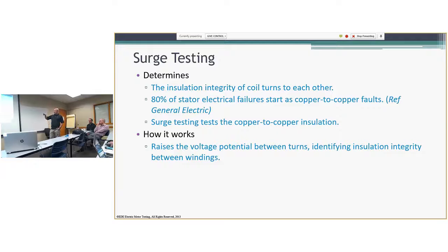So we raise the voltage potential between the turns, and we're chopping up a DC signal really fast, sending it into the winding, and reading that response coming back into the tester. By looking at that waveform, we can tell if there's a problem or not.